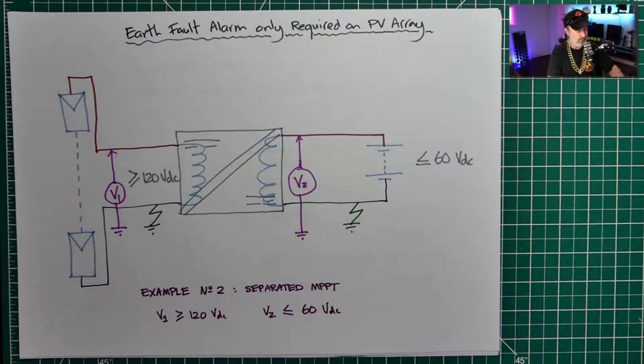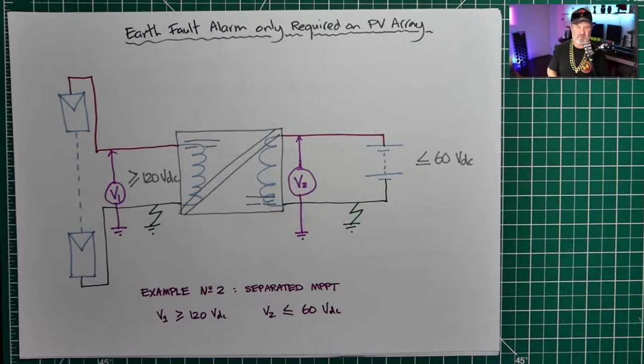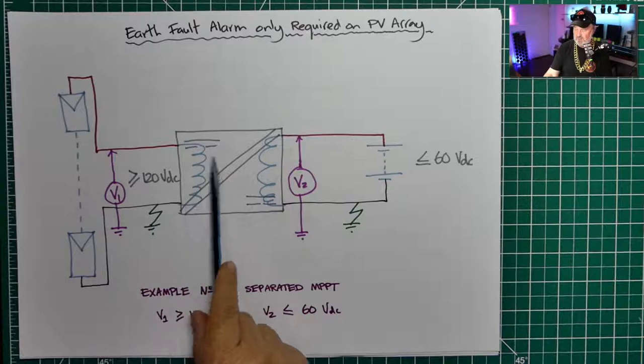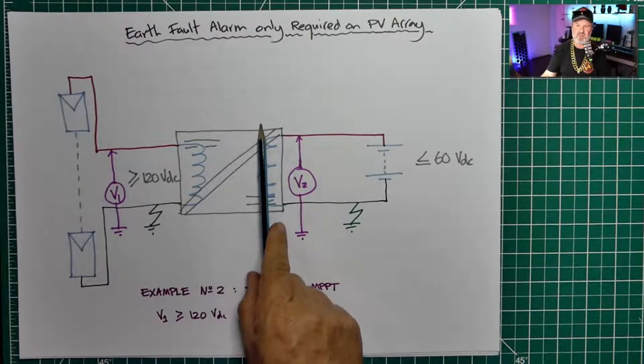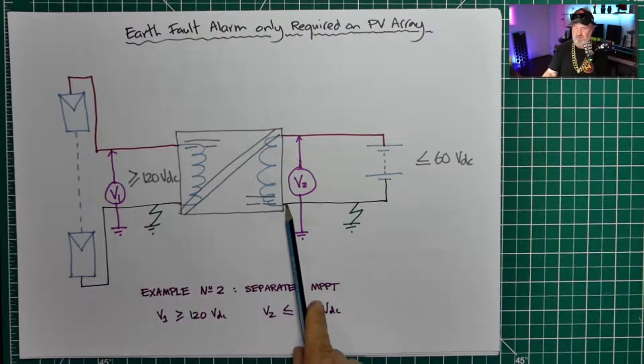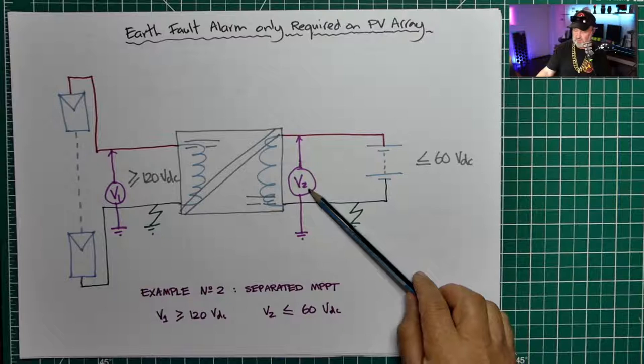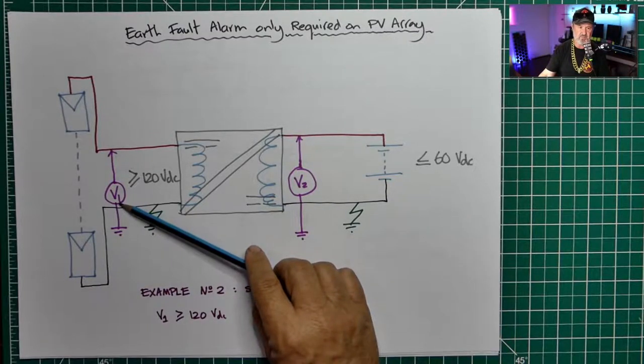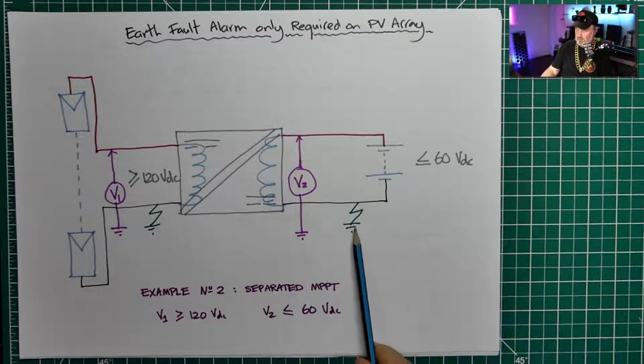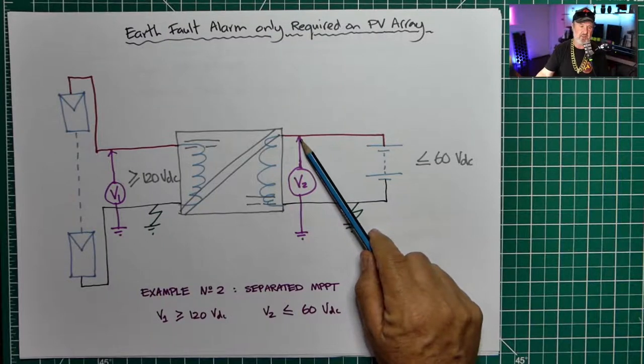Now here we've got a separated MPPT — not so common. My guest might be able to tell me which ones have galvanic separation available on the market in Australia. If it does have galvanic separation — shown here as an isolating transformer inside — that means electrons on the PV array side can't cross over to the electrons on the battery side. Therefore the battery's voltage determines V2 and the PV array voltage determines V1. If we have an earth fault on this side, we're not going to see the PV array voltage appear on the battery port.